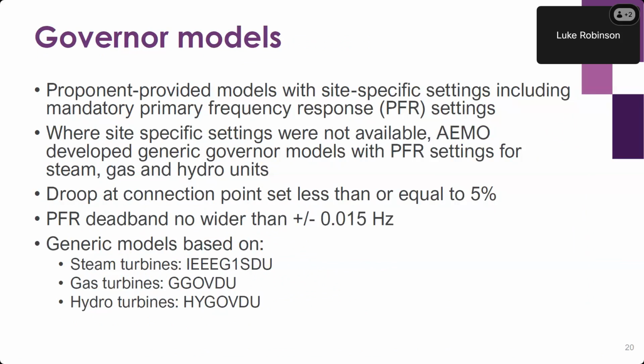As mentioned before, we've also updated the governor models in our studies. So when considering primary frequency response in the risk review studies, AEMO has proponent-provided governor models for a large number of the machines that include site-specific settings indicating the primary frequency response. However, in some instances, the site-specific information isn't available or it may not be up to date, meaning that the performance of that machine could be overestimated or underestimated.